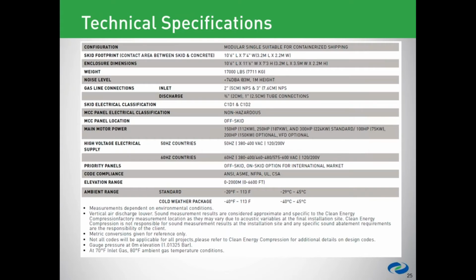What are the liquid and hydrocarbon dew point temperature requirements for the incoming gas at compressor inlet? So that's a really good question, and it does depend on the region that we're operating in. Essentially, that temperature needs to be below the minimum expected temperature of that region. So in general, in Canada, we say that's got to be minus 40 degrees. Some areas in Latin America or Africa, for example, where the temperature never gets below 10 degrees, we could accept temperatures of 0 degrees, for example, because the issue is you never want to be operating in the region or at the temperature that you could have heavy hydrocarbons dropping out of the gas stream.